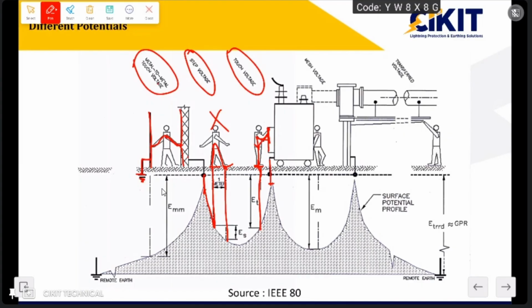The fourth important type is the transferred voltage. In this case, if you take a particular substation, there will be certain components traveling from outside the substation to inside the substation. For example, some pipelines will be laid from outside to inside the substation, and we will be grounding this pipeline at different points. So the pipeline voltage will be different from the potential inside the substation. If some person standing inside the substation makes contact with this pipeline, because of this difference in potential he may get electrocuted. This is considered transferred voltage, and it comes into the picture when he is making contact with structures or pipelines that travel from the substation to other objects. So when working with a substation, we have to keep all these parameters in mind to ensure the safety of the person is maintained.